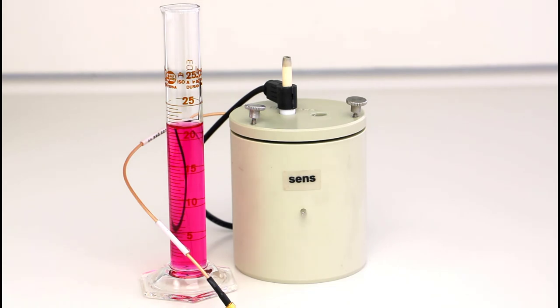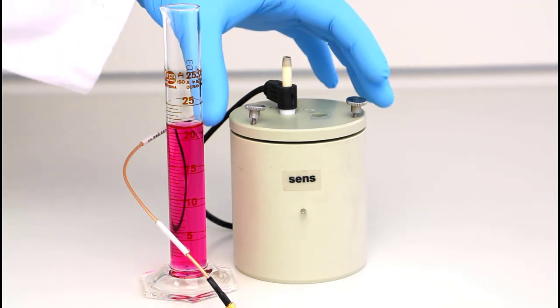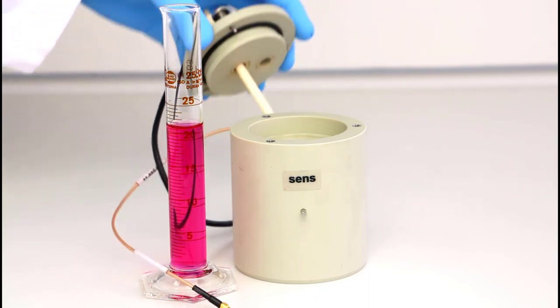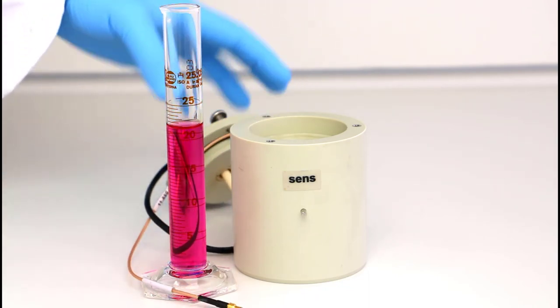The electrode components can be stored dry after cleaning, and it is pretty robust against overloading and titration-disturbing side components in the sample.